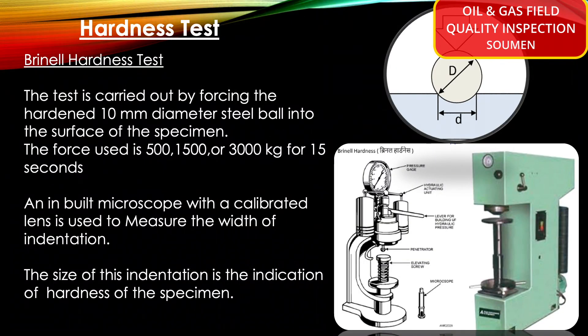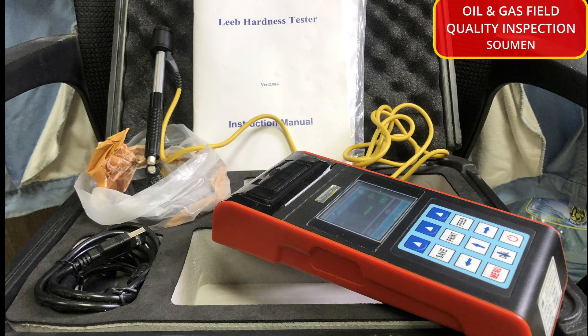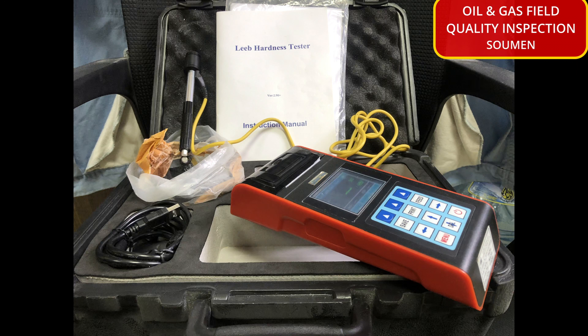The Brinell hardness test is carried out by pressing a hardened 10 mm diameter steel ball into the surface of the specimen. The force used is 500, 1500, or 3000 kg for 15 seconds. A built-in microscope with a calibrated lens is used to measure the width of the indentation. Nowadays, portable pin-type hardness testing machines are also available, generally used for measuring hardness especially in the case of second-time weld repairs, though they are less accurate than the larger machines.